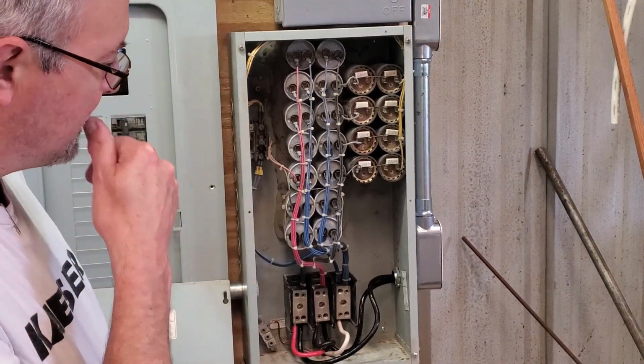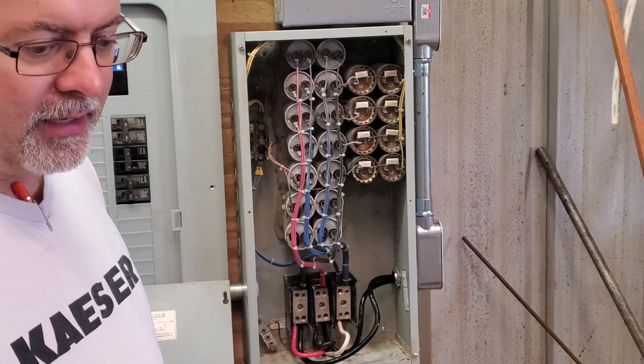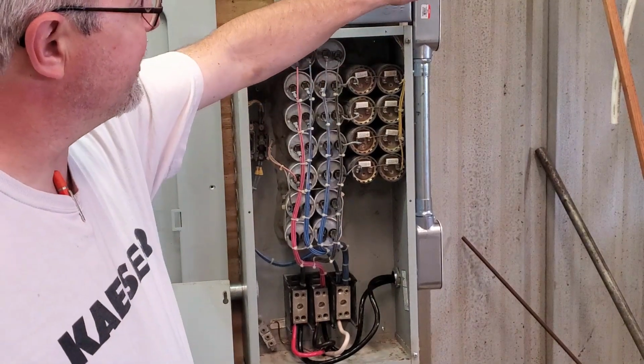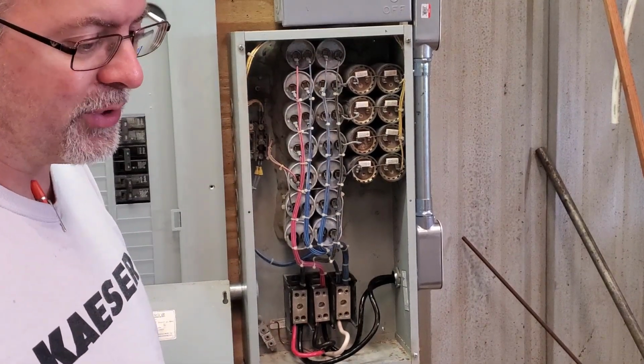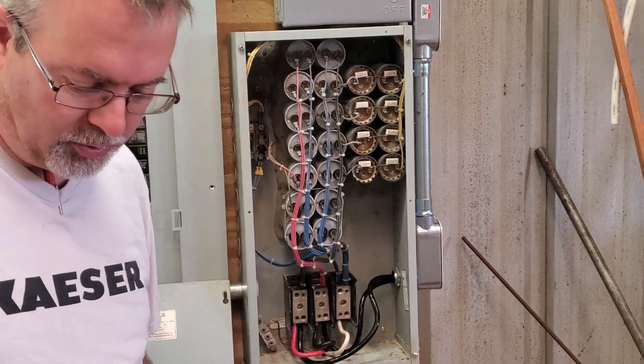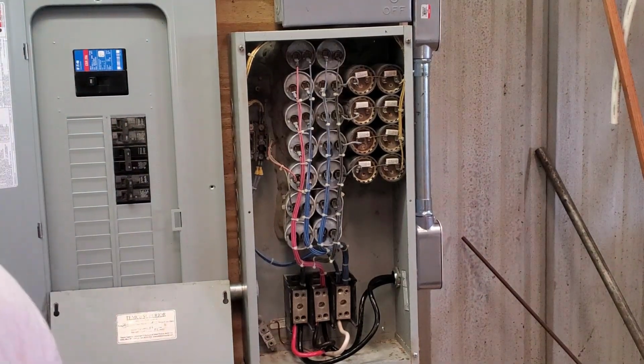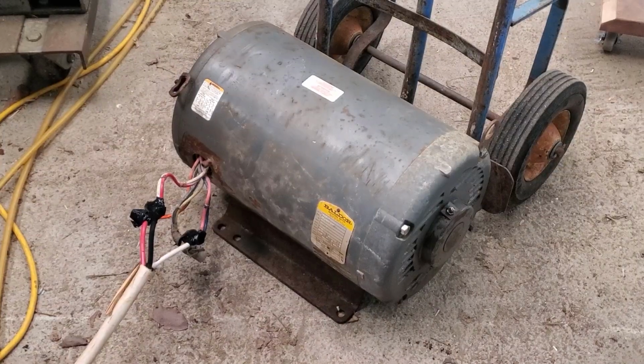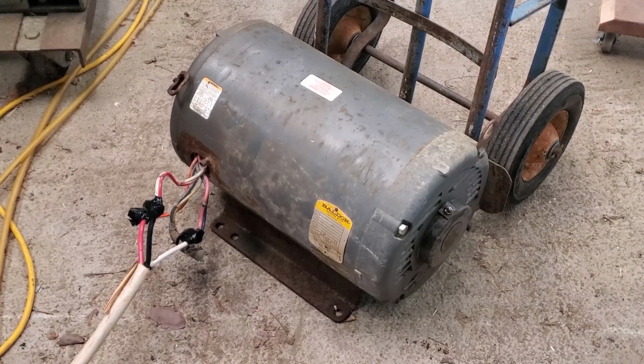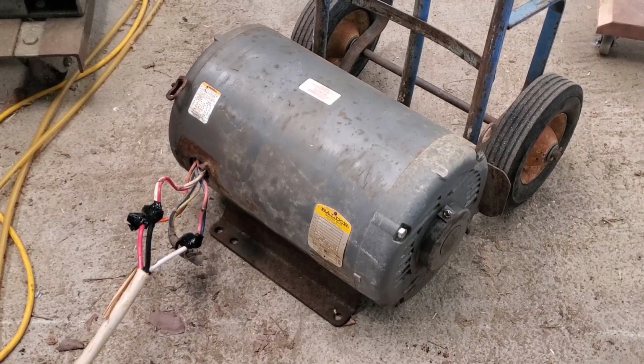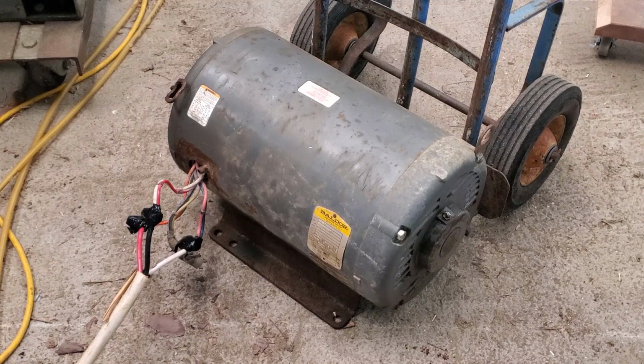So I'm going to power up, and I'm going to test this for the first time - throw this switch on and see if our rotary phase converter works. Okay, you're going to hear some clunks - that'll be the 100 amp breaker being turned on, and then the disconnect switch turned on to power up the rotary phase converter.